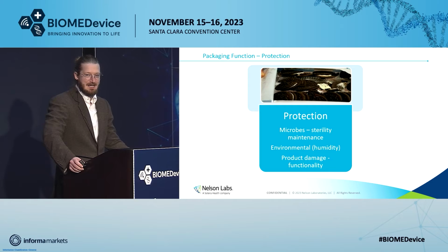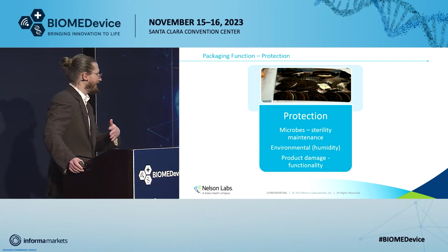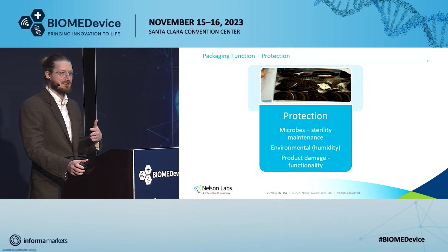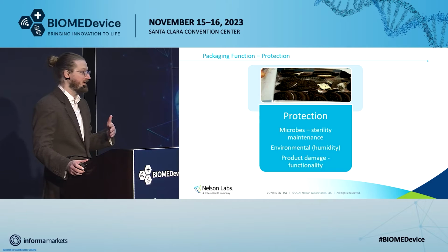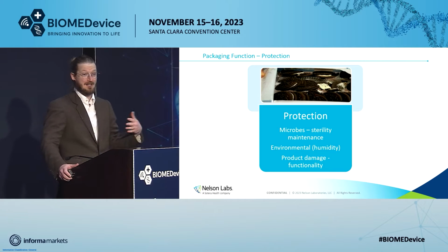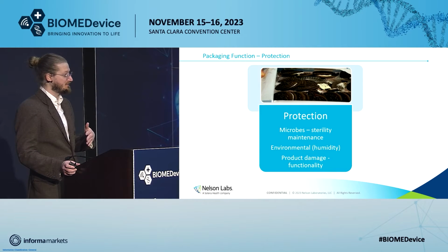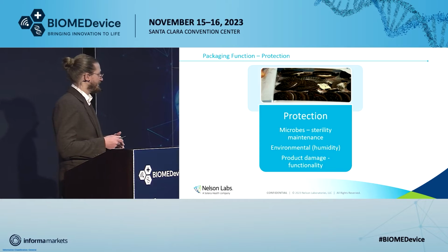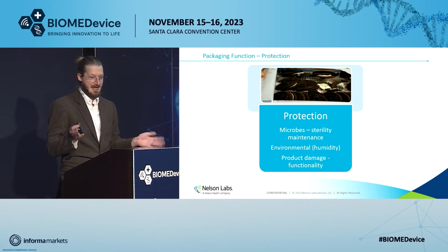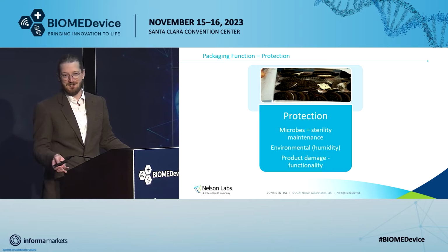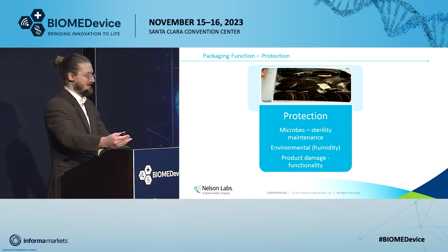It's supposed to maintain sterility, right? You want to keep those pesky microbes out. You want to make sure that if the layers to your sterile barrier system need to offer any sort of protection against humidity, maybe you have electrical components or other things that would react poorly with the additional moisture, that needs to be considered when you're creating your sterile barrier system to keep those environmental factors out. And ultimately, too, your product has to be functional by the time it gets to the point that you use it, right?